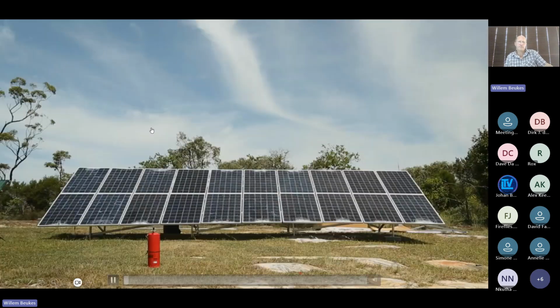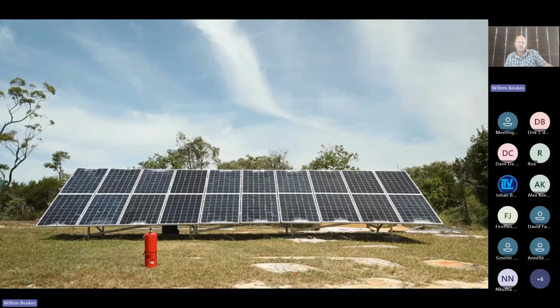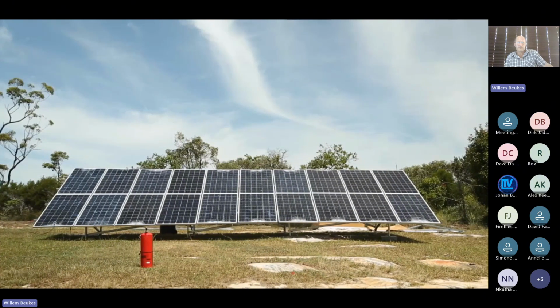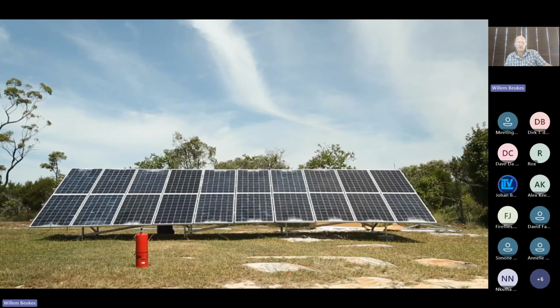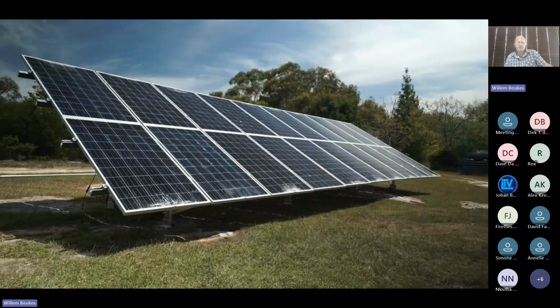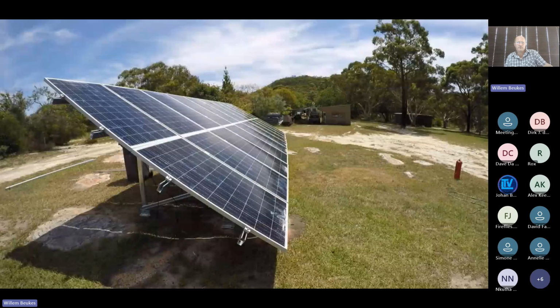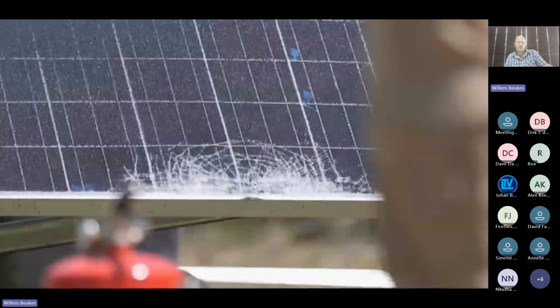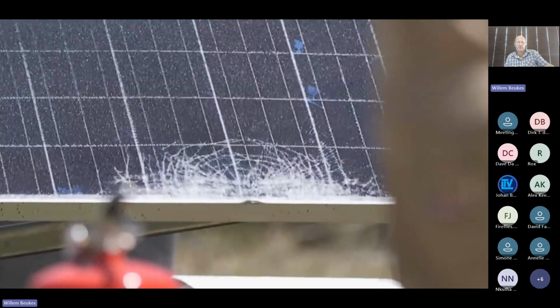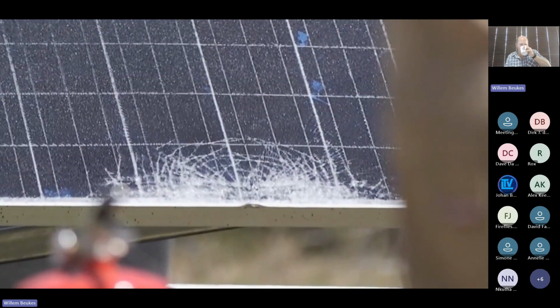A common misconception is that solar panels stop working if the panels are damaged or broken. In this demonstration, we've connected a series of 20 250 watt solar panels to create a 5 kilowatt solar system. If you look closely at the panels, you'll notice that the glass in each panel is shattered to simulate the damage that might be caused by an event such as a hailstorm.